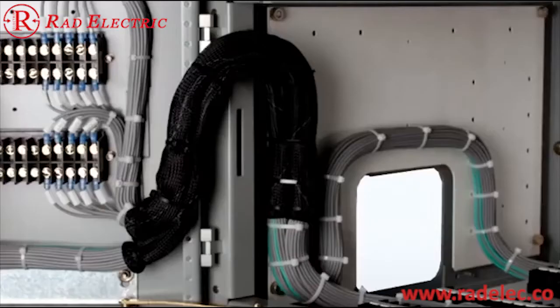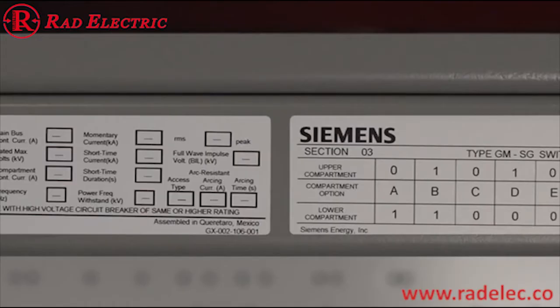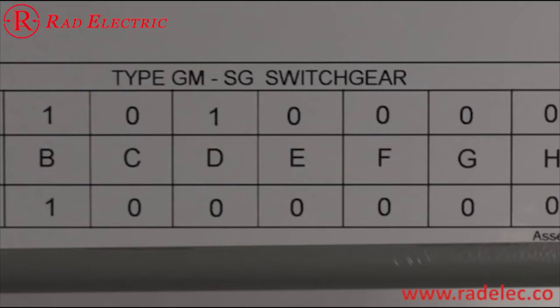Siemens GMSG switchgear also features a low-voltage auxiliary compartment. The auxiliary compartment has removable white interior mounting plates. The white finish makes it easy for installation and service personnel to locate wires. Fuse blocks, terminal blocks, interposing relays, auxiliary relays, and other devices can be mounted to these panels. You'll notice there are two labels on this compartment. The rating label describes the type and configuration of the compartment and the ratings of that particular GMSG skeleton section.